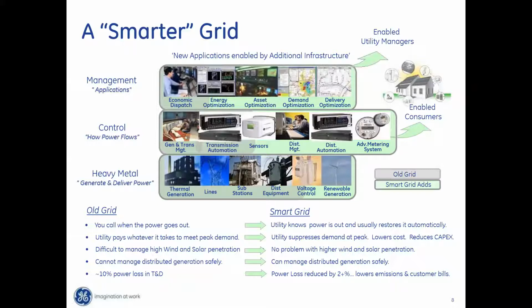In the middle, you can see sensors is shaded halfway. We've been adding instrumentation to the grid for a long time, but today what's exciting is we have specialized sensors we can add to the grid. This sensor I'm showing here, I would take the oil from the main tank of the transformer and put that oil through this sensor. And the sensor can detect different gases that are dissolved in that oil. And there's different failure modes that can occur in a transformer that generate a specific gas, like ethane, acetylene, methane.